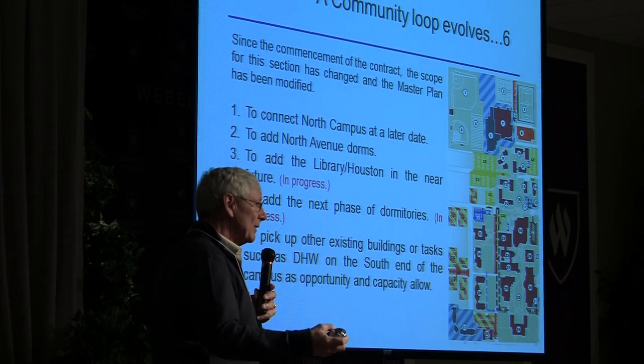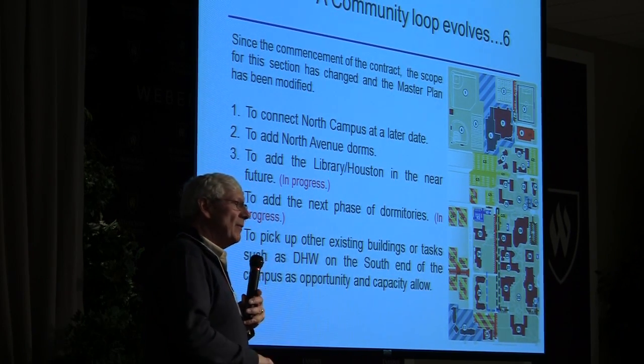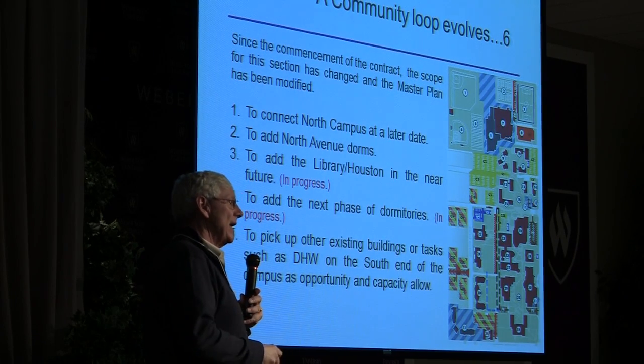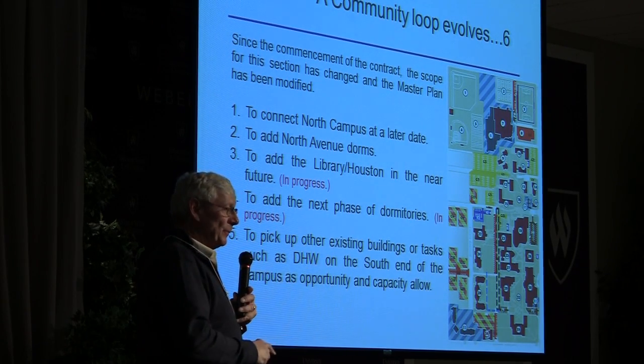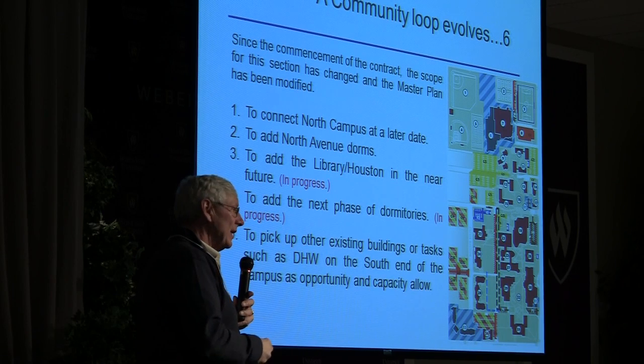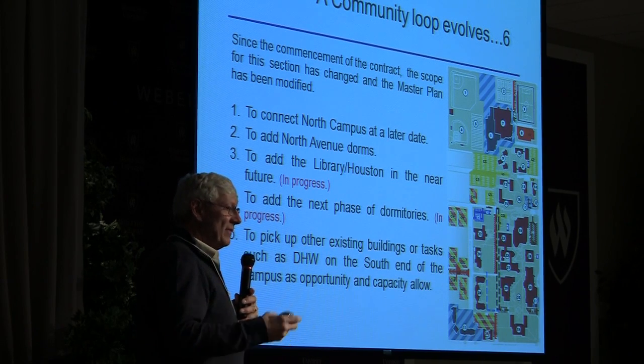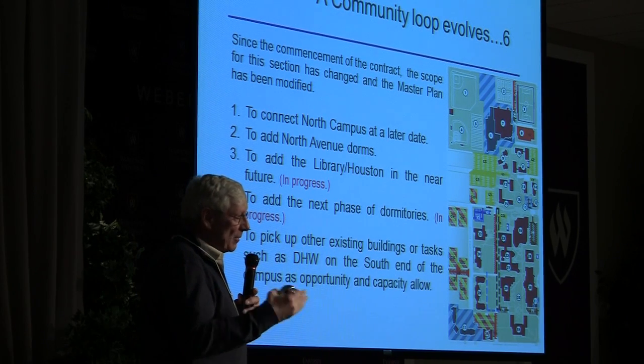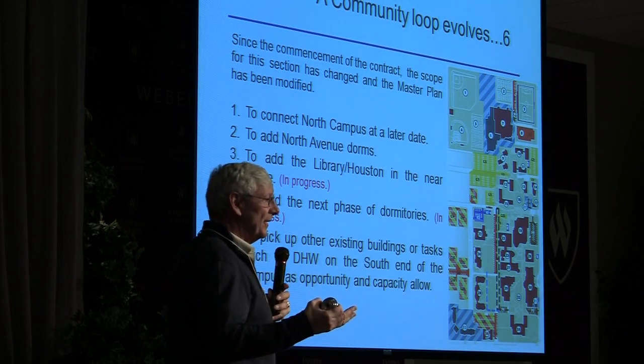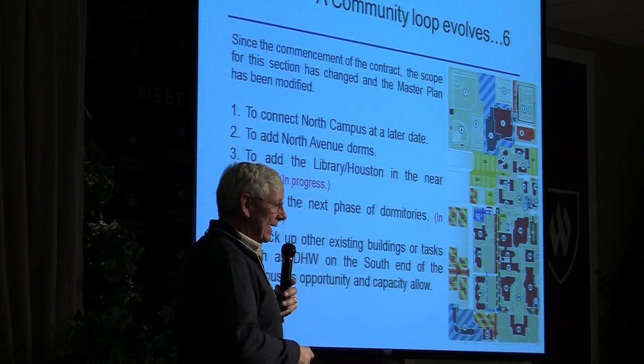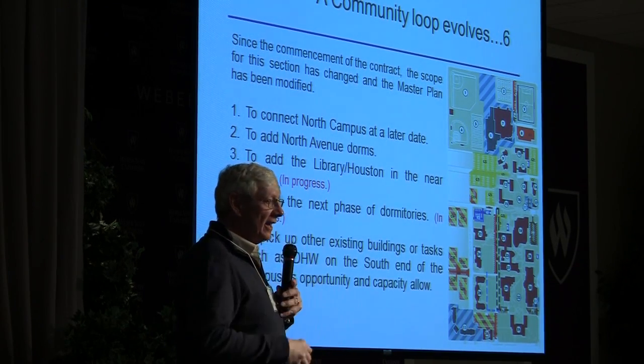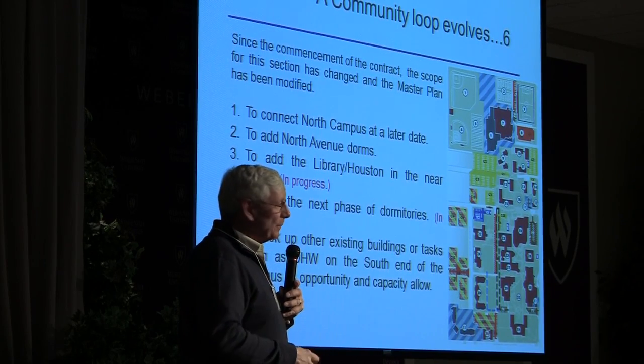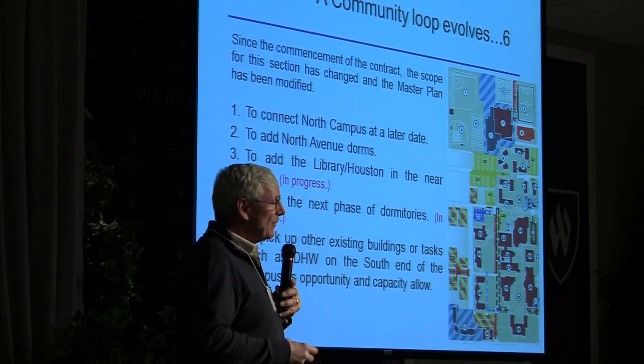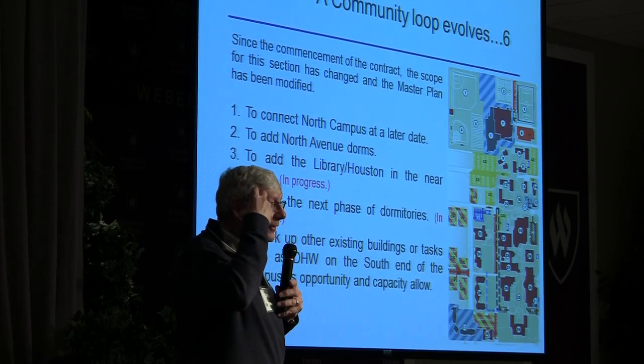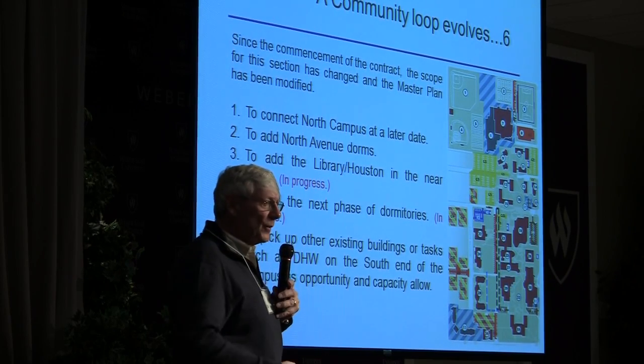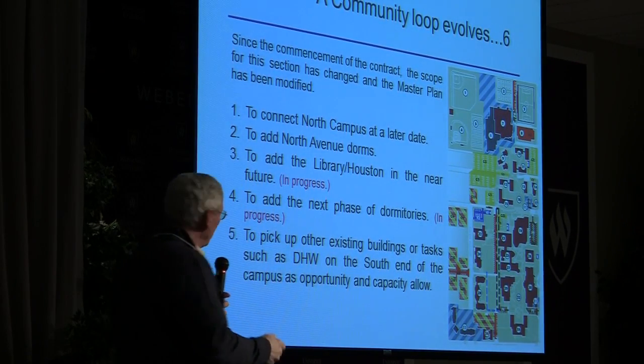We figured we'd need somewhere in the neighborhood of 5,000 to 6,000 gallons a minute at peak going through this building. One of the fun things we'll see is we've never gotten over about 3,500 gallons in that system. Right now it's idling along, we've got a 40 horsepower pump on the main side, we're at 30%, so do the math, we're using 8 plus horsepower to move that energy.